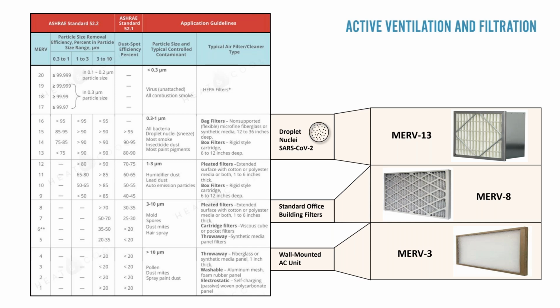And you might note as we go through the different items today that there is almost a reverse relationship between some of these strategies and what you would do to make a building more energy efficient. A lot of the ideas, a lot of the suggestions here will increase the amount of energy the building consumes. So a key aspect of all of it is flexibility. We want the ability to make changes to deal with the high risk that we're dealing with now, but have the ability to revert back to a condition where perhaps we have less filtration capability, but better energy efficiency when the risk drops back down, which it will.